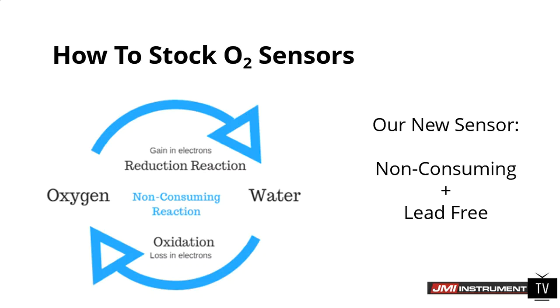So when we say not consuming, you see this makeshift recycle logo in front of you. We have a non-consuming reaction. What actually happens is the oxygen molecule goes into the sensor, adds an electron and creates water within the electrolyte. And because we changed the anode and cathode material from lead to a proprietary material that doesn't oxidize under this chemical reaction, we don't have any depleting sensor with this oxygen sensor.